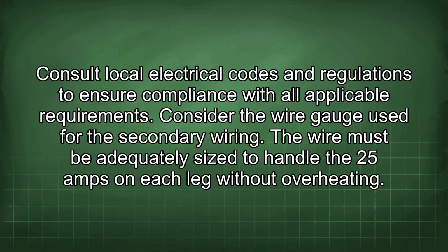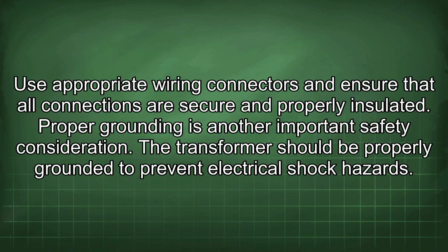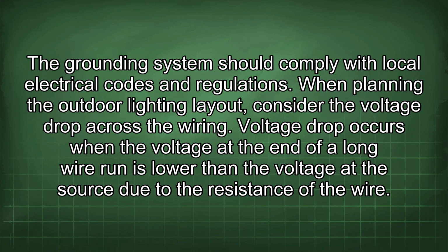Consider the wire gauge used for the secondary wiring. The wire must be adequately sized to handle the 25 amps on each leg without overheating. Use appropriate wiring connectors and ensure that all connections are secure and properly insulated. Proper grounding is another important safety consideration. The transformer should be properly grounded to prevent electrical shock hazards. The grounding system should comply with local electrical codes and regulations.